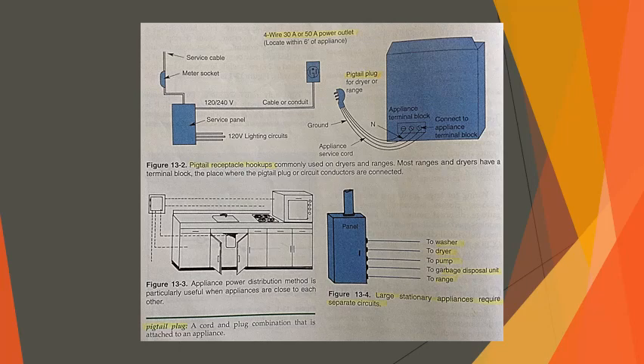Still another method used is the system illustrated in figure 13-3, bottom left. Here, provided the appliances are close to one another, a high amperage appliance power panel is installed. The various appliance circuits are run from this sub-panel at 20 amps each. This works well in kitchens with built-in units or in utility rooms. In general, the hookup for a range is a 3- or 4-wire pigtail plugged into a 50 amp heavy duty receptacle. The fourth terminal is for the equipment ground.